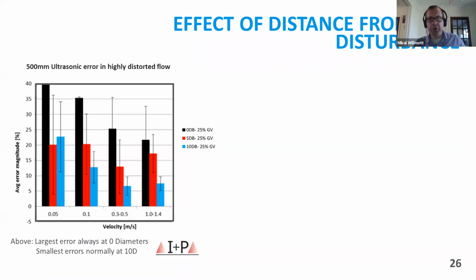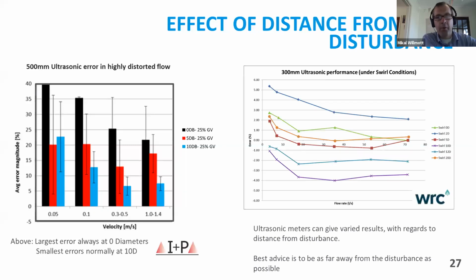Now, we'll show you some results that WRC did for us last year. We just want to hit the button, Andy. Okay, so they've made their main have some swirl in it. And what you'll see is the best results happen at 20 diameters down from the last disturbance. Then it's 5 diameters. And then you might be a little bit surprised, it's 0 diameters. And then it's 12 diameters. And then the worst case scenario is either at 2 diameters or 10 diameters, depending on what flow rate you're looking at.